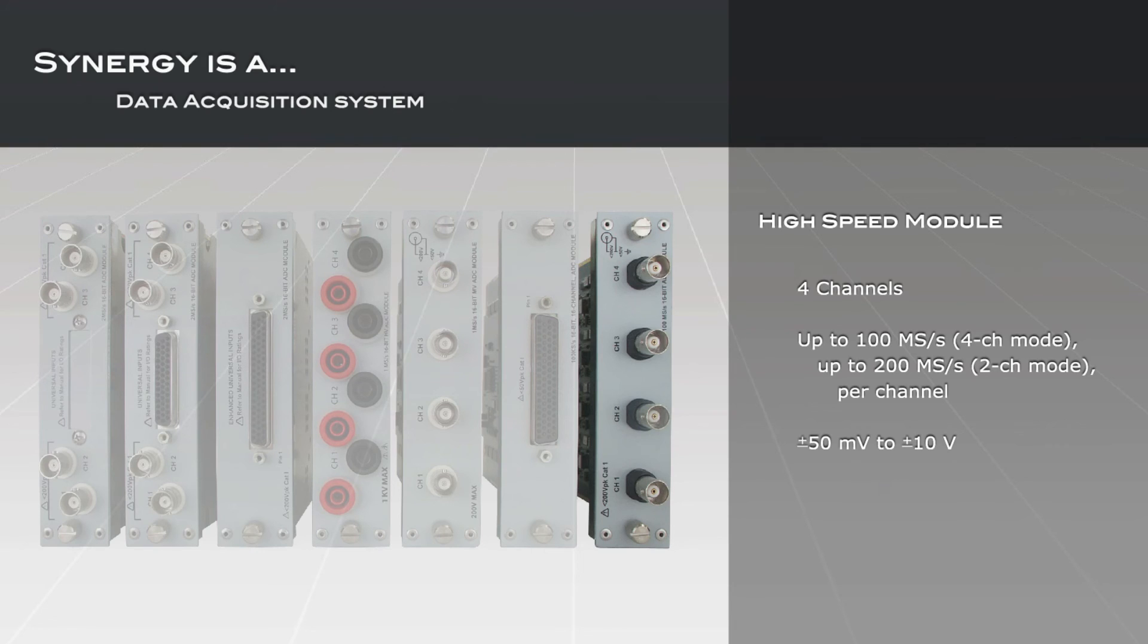The high-speed input module provides 4 channels of 100 mega-samples per second per channel or 200 mega-samples per second digitizing using a proprietary interleaving technique employing 16-bit digitizers. Differential high-impedance 20 megahertz amplifiers support voltage ranges from 50 millivolts to 10 volts.